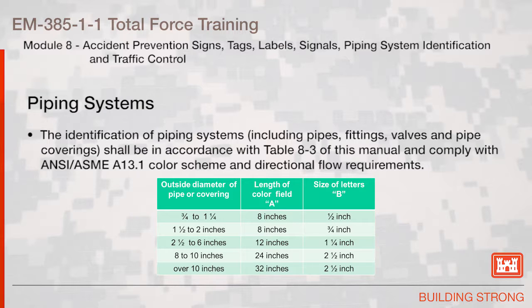The identification of piping systems including pipes, fittings, valves, and pipe coverings shall be in accordance with Table 8-3 of this manual and comply with the ANSI/ASME A13.1 color scheme and directional flow requirements. This table, which is organized by pipe diameter, indicates the length of the color field and the size of the lettering required.